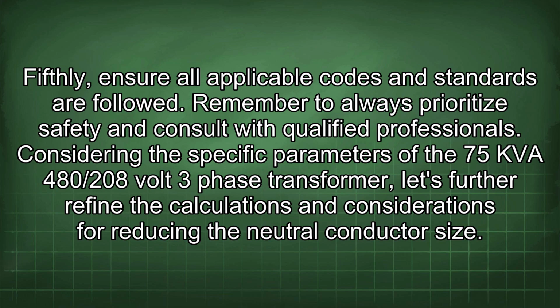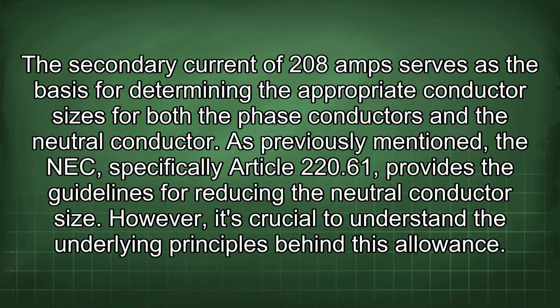Considering the specific parameters of the 75 kVA 480/208 volt 3-phase transformer, let's further refine the calculations and considerations for reducing the neutral conductor size. The secondary current of 208 amps serves as the basis for determining the appropriate conductor sizes for both the phase conductors and the neutral conductor. As previously mentioned, the NEC, specifically Article 220.61, provides the guidelines for reducing the neutral conductor size.